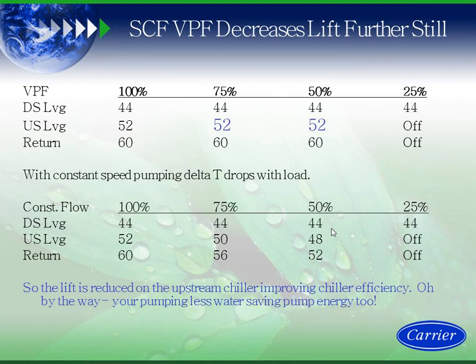Now let's look at going to variable primary flow. So now I have a constant flow pumping system or a variable primary flow system. Now when I go variable primary flow, I'm able to maintain my delta T. If we look at a constant flow system, so I have a variable primary flow on top, I'm maintaining a delta T throughout the load. Whereas on a constant flow system, my delta T drops as the load drops. As the load drops, I would actually pay a penalty in efficiency if I was doing a series counterflow. But if I do series counterflow variable primary, I actually increase my efficiency by going to variable primary flow because I reduce the lift on the upstream machine. That's the key piece.